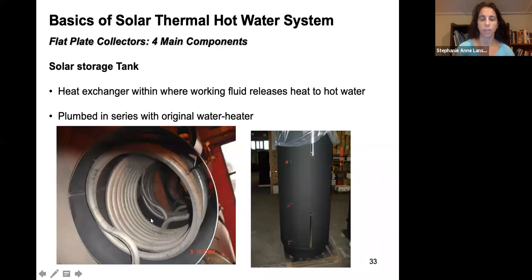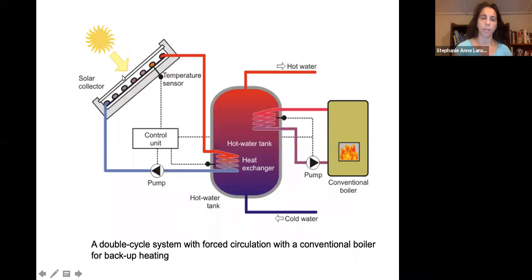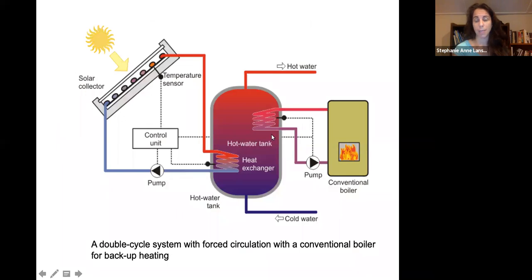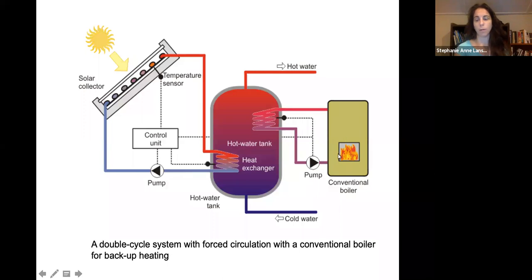Finally, the solar storage tank is where the working fluid releases heat to the hot water supply. It is often plumbed in series with the original hot water heater. You might have two separate tanks or one combined tank with a conventional boiler, so the solar system heats the water most of the way and the boiler only needs to work a little to reach the desired temperature for showers.